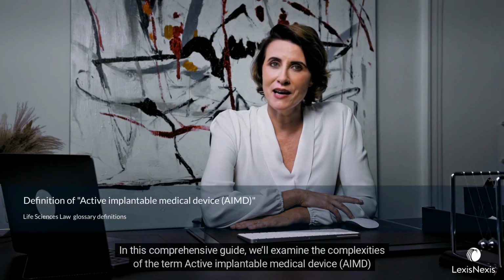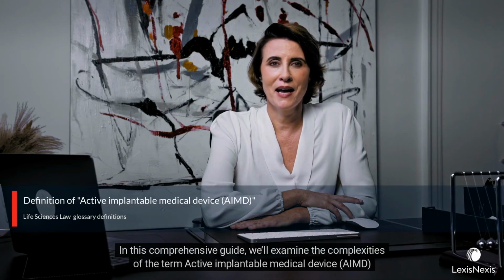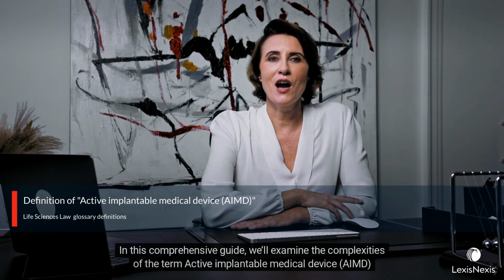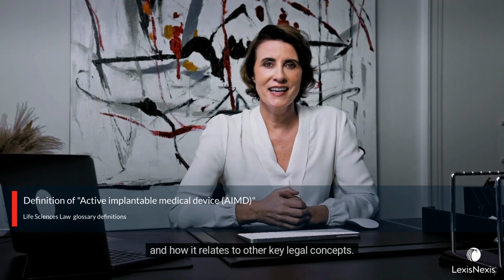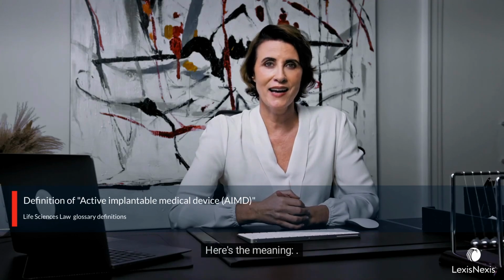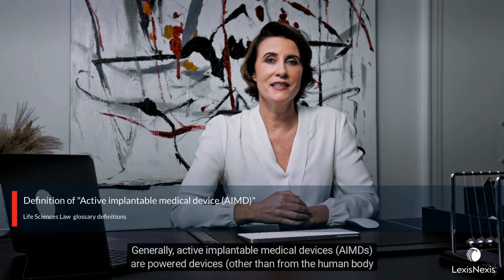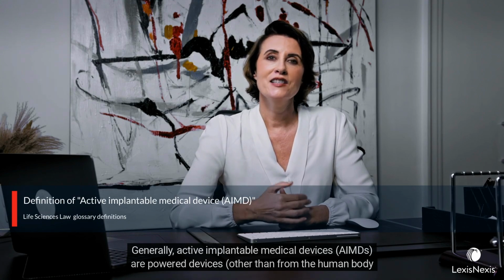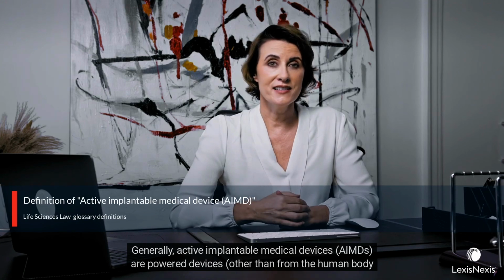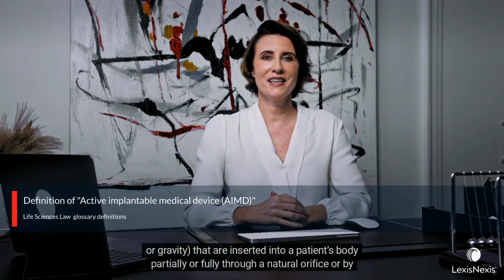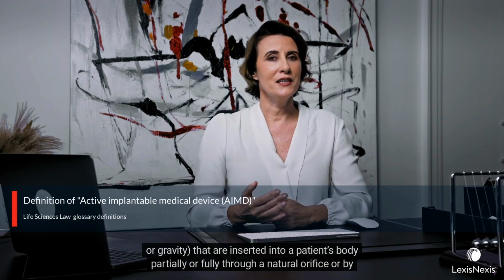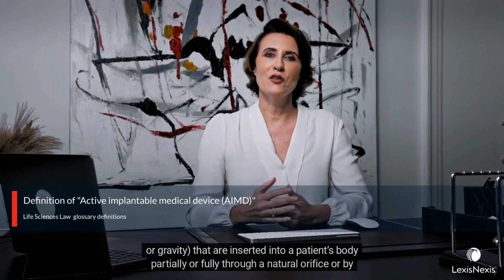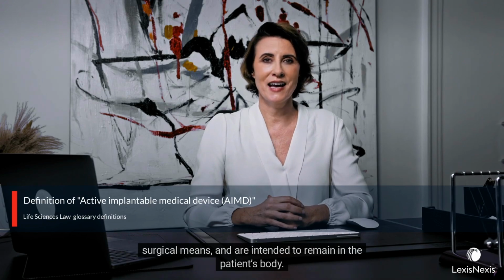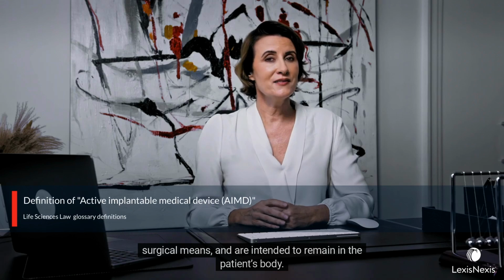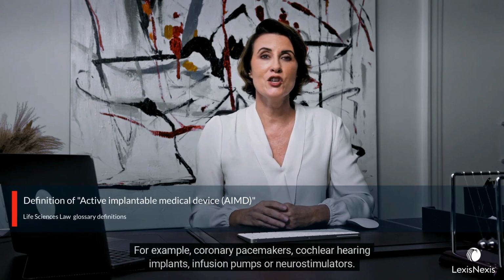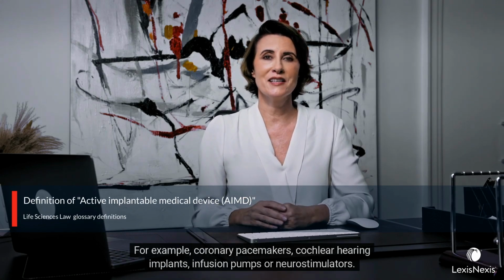In this comprehensive guide, we'll examine the complexities of the term active implantable medical device, AIMD, and how it relates to other key legal concepts. Here's the meaning. Generally, active implantable medical devices, AIMDs, are powered devices, other than from the human body or gravity, that are inserted into a patient's body partially or fully through a natural orifice or by surgical means, and are intended to remain in the patient's body. For example, coronary pacemakers, cochlear hearing implants, infusion pumps, or neurostimulators.